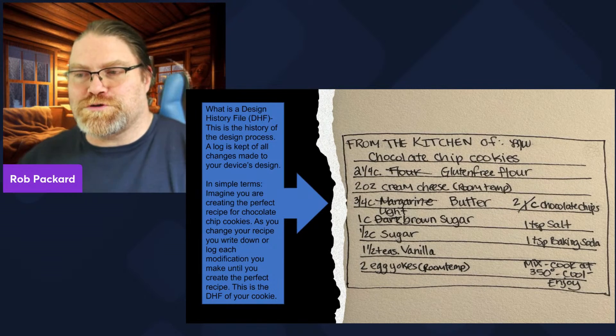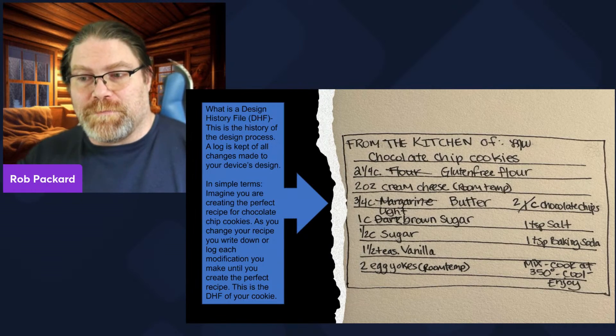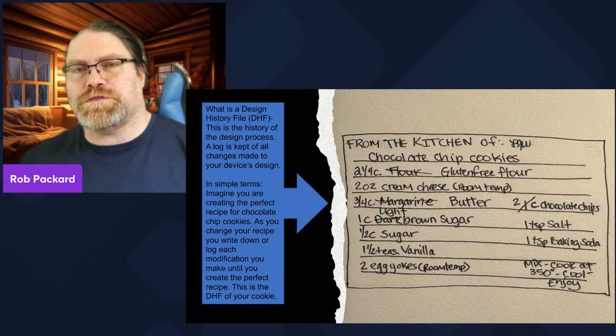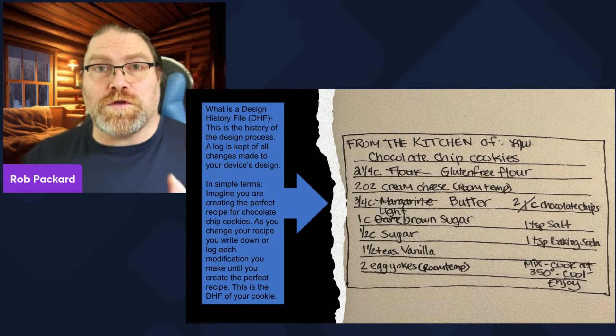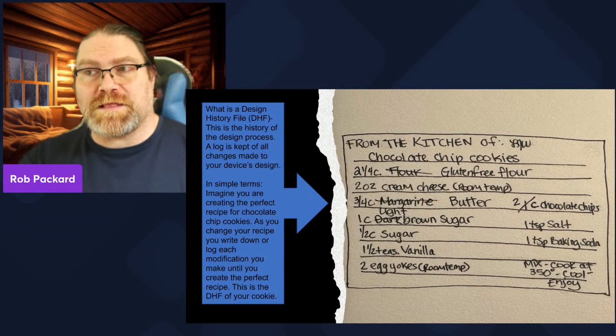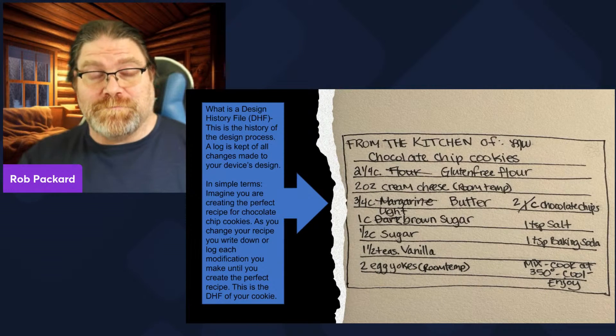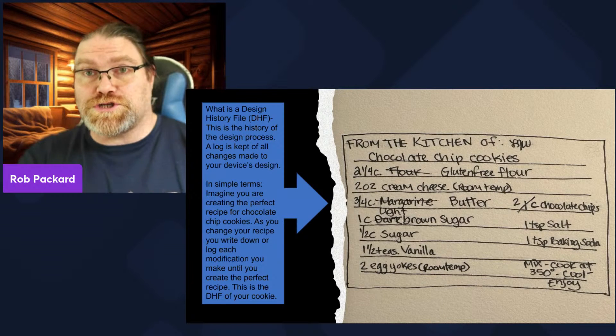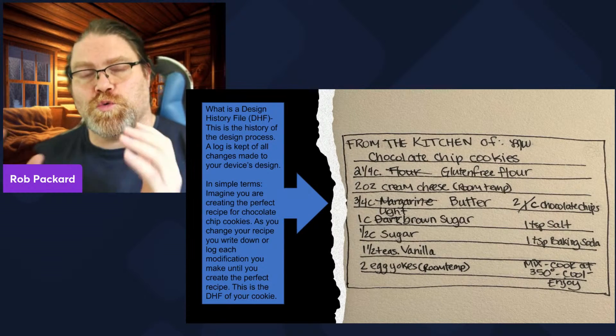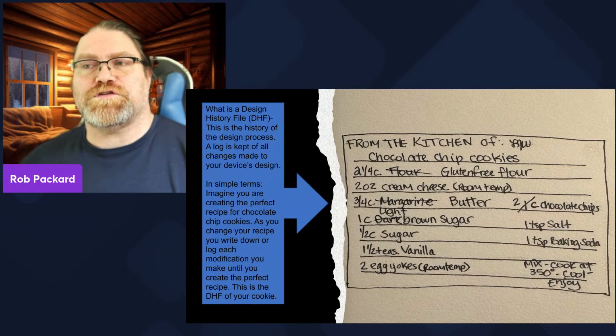This is the approach to design — they just want to know how you got there. All those meeting minutes from every design team meeting go in an appendix, but you document them. You have formal design reviews — you're only required to have one, but you can have one at each phase. Whatever your plan says, that's what you do. Your design history file is the evidence that you followed your plan. As your plan changes, you document that — your inputs change, your outputs change. Your verification and validation hopefully won't change because that costs a lot of money. All of those records go into one file — a really big Dropbox folder or 28 binders. That is your design history file.